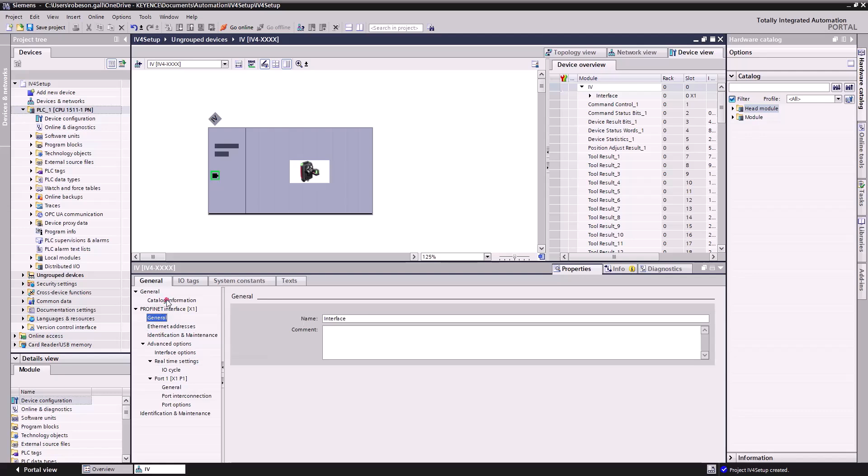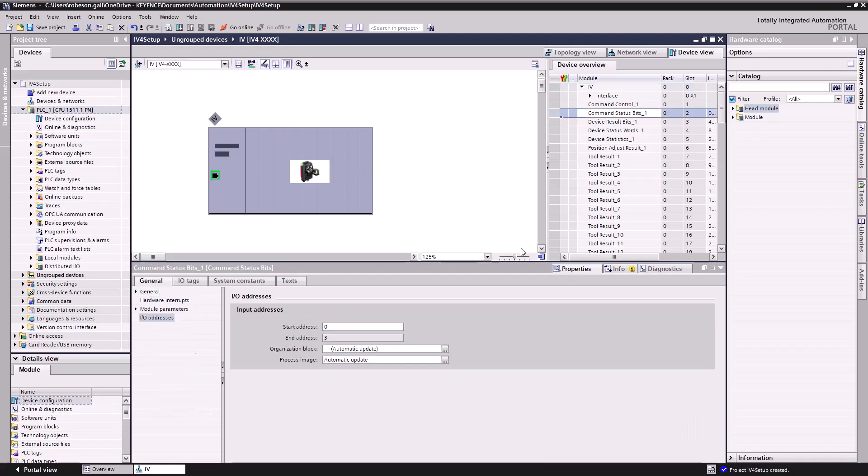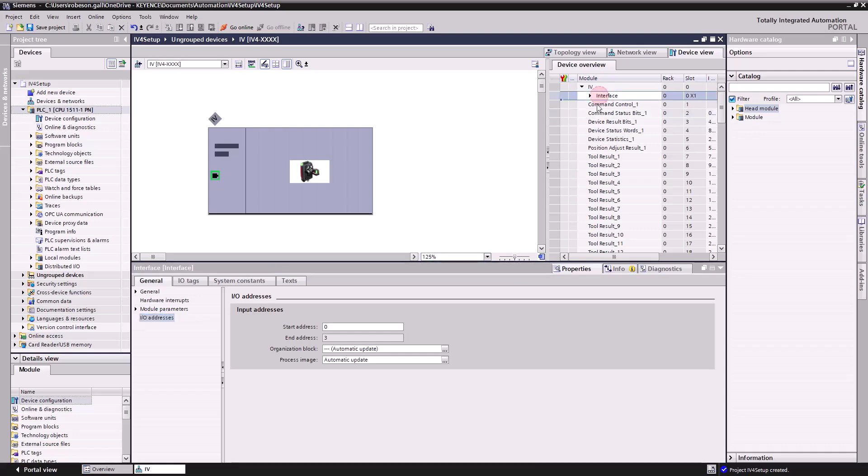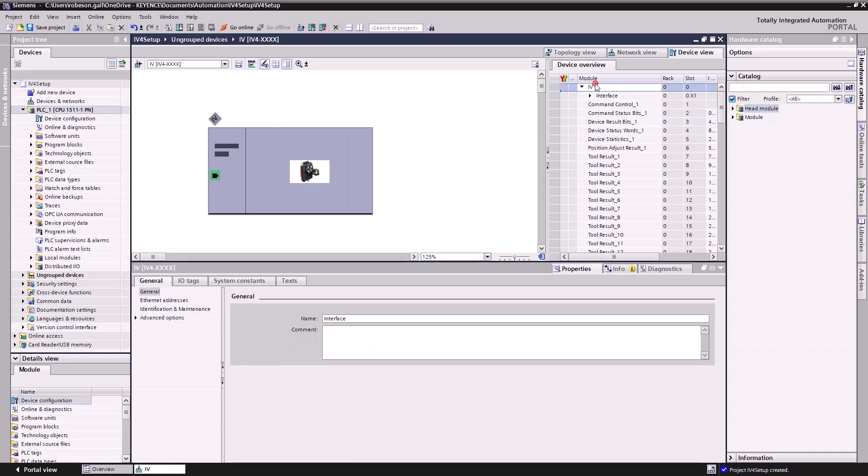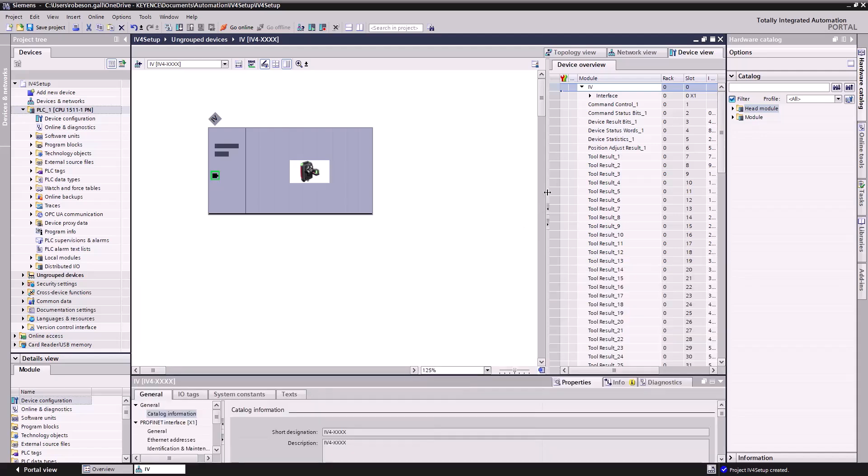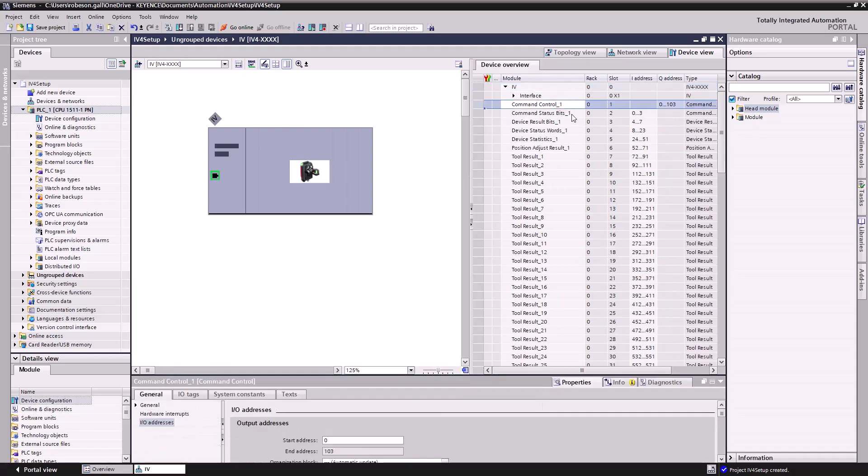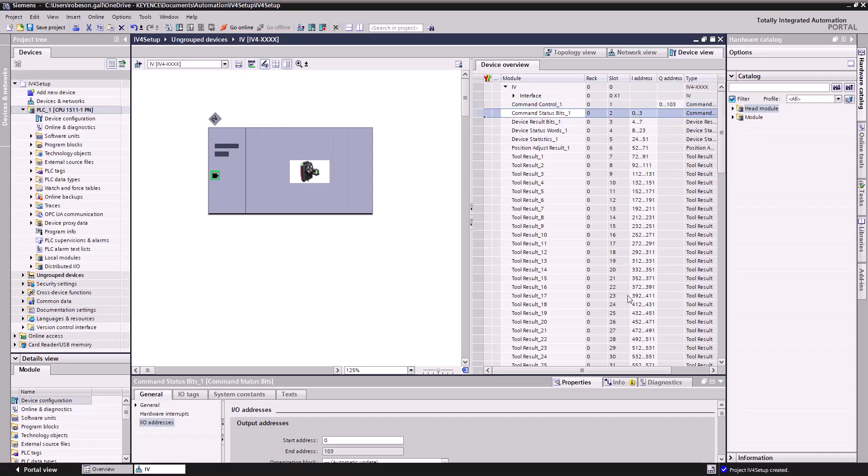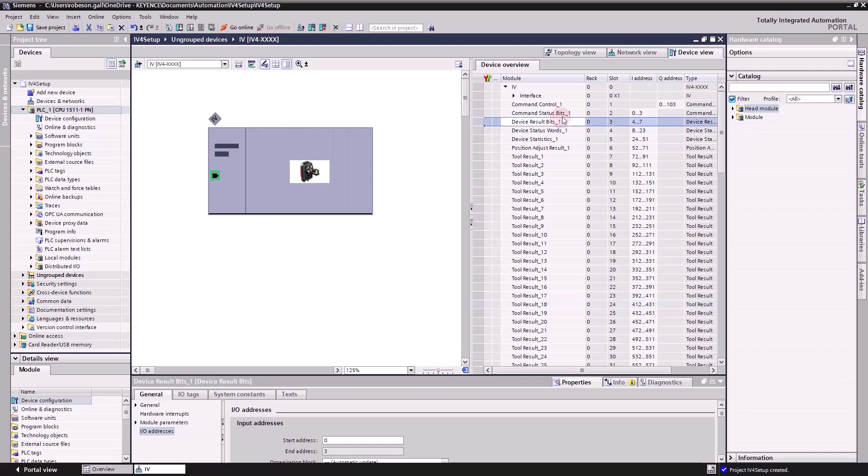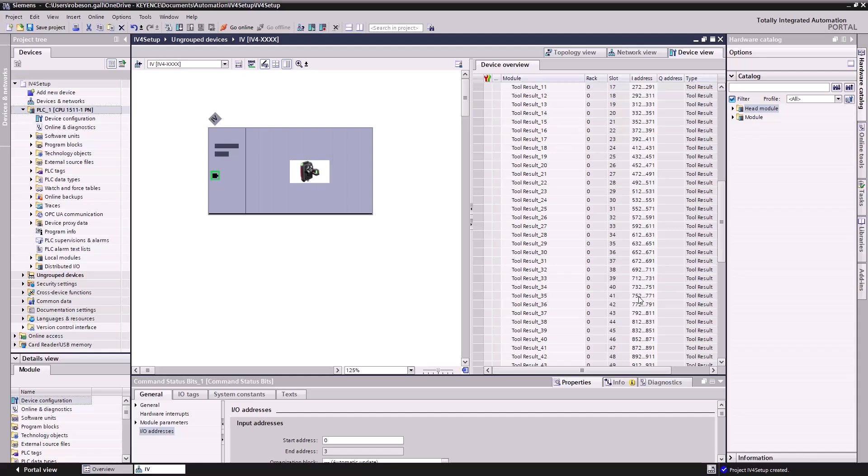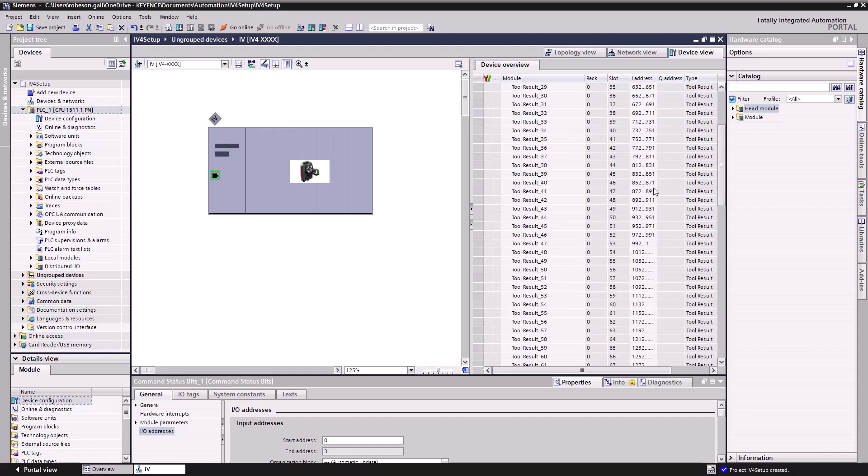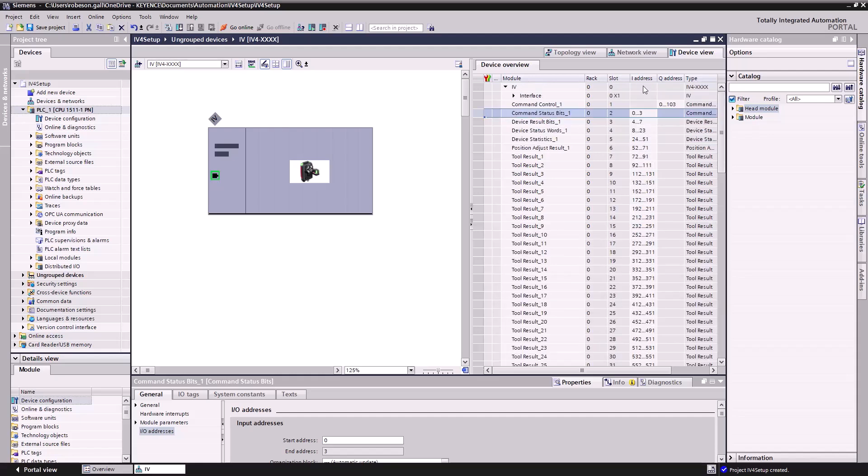General is the interface. Yep, this all looks good to me. Now you'll see when we loaded in our IV4, we actually have all of these different organizations, categories of bits here. We have our command control, which is in our Q address for our outputs 0 to 103. And everything else is going to be inputs. So command status bits, device status words, etc. These are going to take up a good amount, a good chunk of space in there in your addresses.